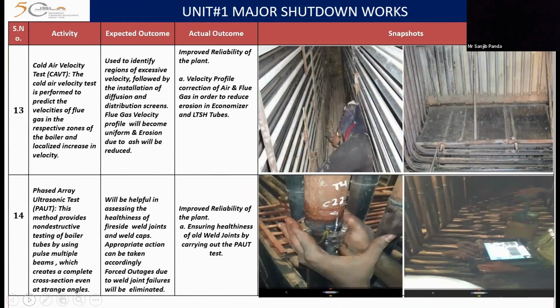In the boiler side also, we have done the cold air velocity test and phase array ultrasonic test. The cold air velocity test has been done to predict the velocities of flue gas in the respective zones and to keep it uniform. And PAUT is one of the methods of non-destructive testing by using the pulse multiple beams, which is able to assess the tube welds, and the weakened welds are identified on time and repaired so that the reliability of the unit is increased.